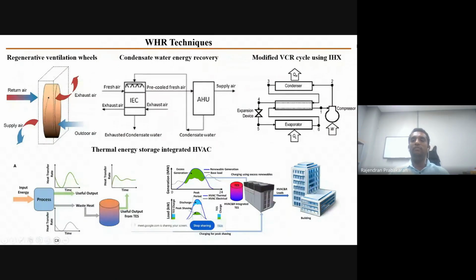And the next one, the modified vapor compression cycle using IHX. Here, the cycle reuses the waste energy within the refrigerant to preheat the refrigerant before the compressor inlet. With this kind of technology, we can increase the system COP significantly. And nowadays, these internal heat exchangers are already equipped in all kinds of VCR cycles. And the last one is thermal energy storage technology.